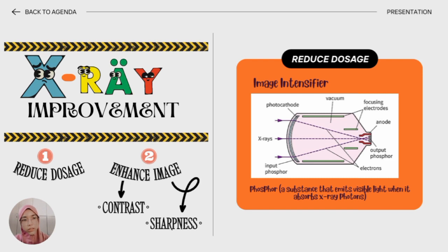Based on the pictures, it shows that incoming X-rays strike a phosphor screen, producing visible light photons, then release the electron by the photoelectric effect. The electron is accelerated and focused by the positively charged anode, strikes the screen and gives out visible light. The image can be viewed and stored. Using an image intensifier reduces the patient exposure by factors of 100 to 500.